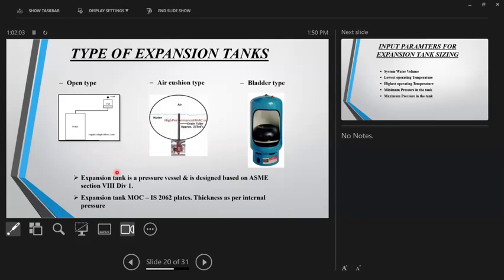Obviously, an expansion tank is a pressure vessel, and it is designed as per ASME Section 8 Division 1. In India, we use IS 2062 plates. I'm not sure what you use in the Gulf regions, but these are MS plates welded together. So this is how the tank looks. It's an ASME pressure vessel.